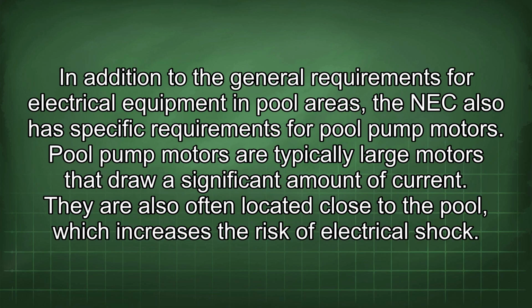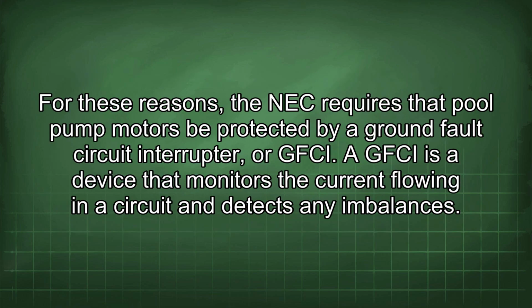In addition to the general requirements for electrical equipment in pool areas, the NEC also has specific requirements for pool pump motors. Pool pump motors are typically large motors that draw a significant amount of current. They are also often located close to the pool, which increases the risk of electrical shock. For these reasons, the NEC requires that pool pump motors be protected by a ground fault circuit interrupter, or GFCI.